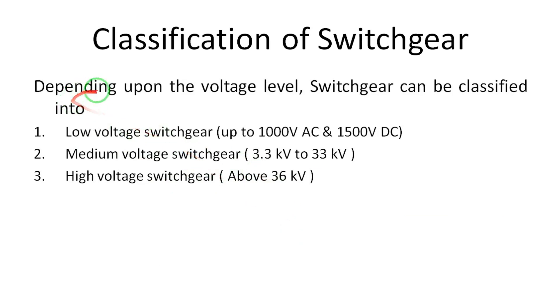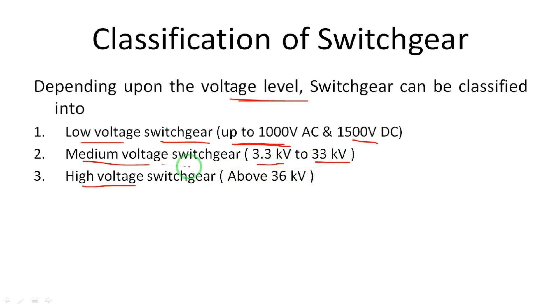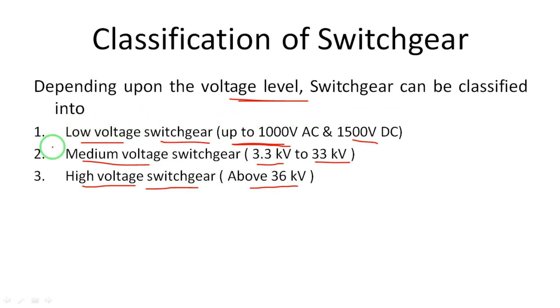Another classification is based on voltage level. There are three types: low voltage switchgear, medium voltage switchgear, and high voltage switchgear. Low voltage switchgear is used for up to 1000 V AC. Medium voltage switchgear covers the range of 3.3 kV to 33 kV. For beyond 36 kV, high voltage switchgear is used. Each of these three systems includes switching, controlling, and protecting parts.